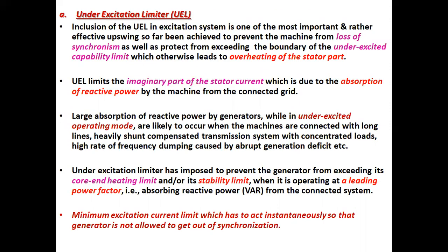Under excitation limiter. Inclusion of the under excitation limiter in the excitation system is one of the most important and rather effective measures achieved so far to prevent the machine from loss of synchronism as well as protect it from exceeding the boundary of the underexcited capability limit, which otherwise leads to overheating of the stator part.